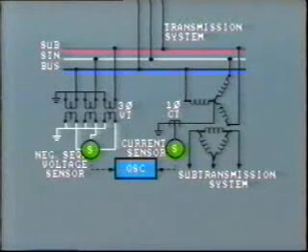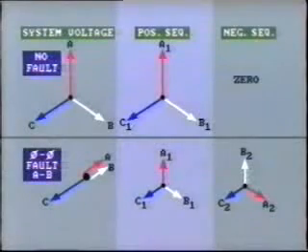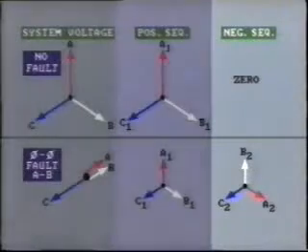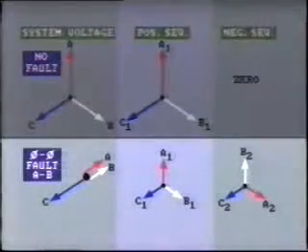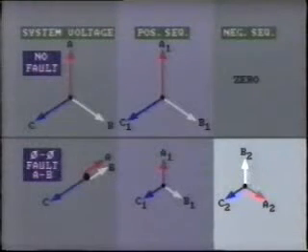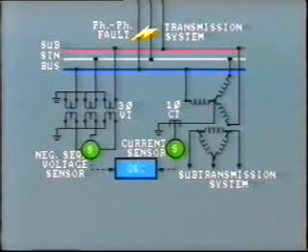We can also use a negative-sequence voltage sensor connected to the bus, which will sense a phase-to-phase fault on any line connected to the bus. A phasor diagram from an earlier lesson shows the voltage broken down into its positive and negative-sequence components. Before the fault, we have balanced three-phase voltages and the negative-sequence component is zero. As soon as the fault is applied between A and B phases, the negative-sequence voltage suddenly increases. So when this sensor detects negative-sequence voltage, we can be quite sure that a fault has occurred and recording can begin.